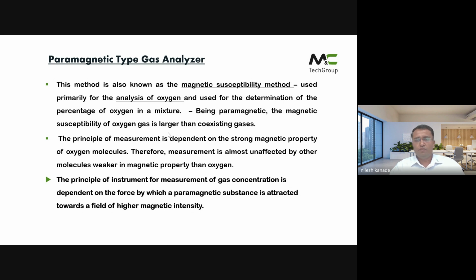In this kind of measuring principle, the gases have paramagnetic properties, like magnetic susceptibility. The gases having the magnetic property produce a magnetic field. So for the measurement of these gases, paramagnetic type sensors are built and these analyzers are used.